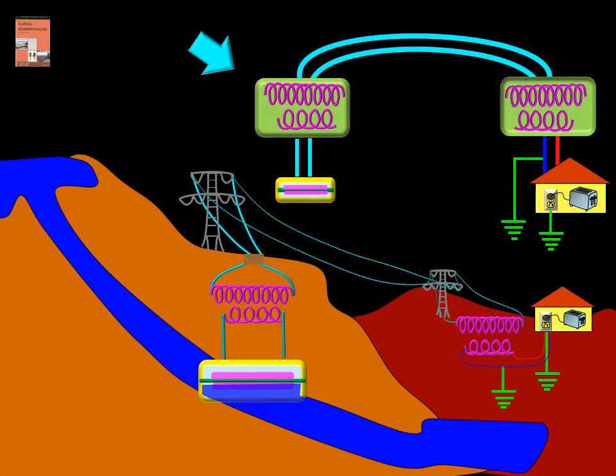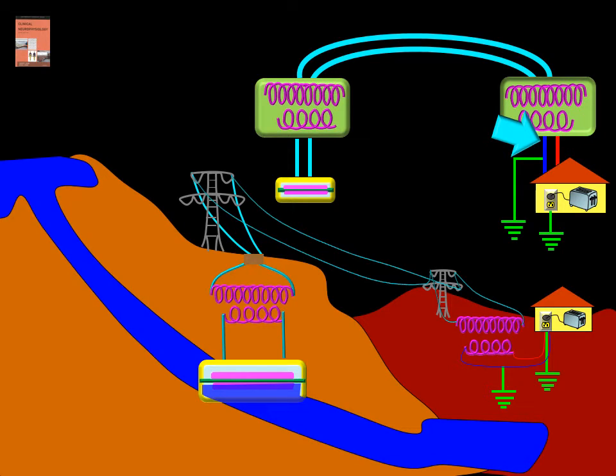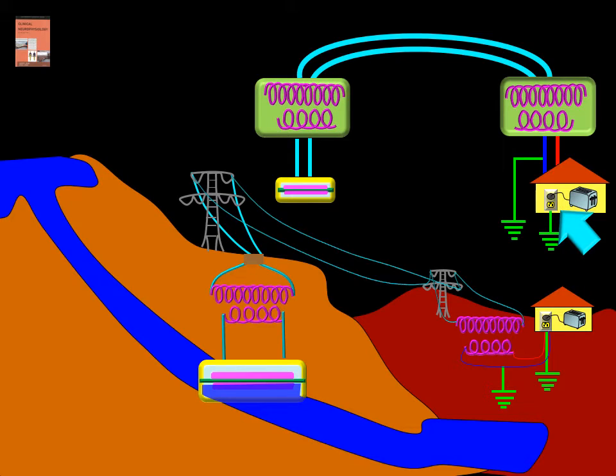The electricity produced by the power plant is boosted to deliver high voltage electricity in the range of 4,800 volts, which is then reduced by a second device to 120 volts, and once reduced to 120 volts it is delivered to the hospital to be available at the wall receptacle for powering hospital equipment. A schematic shows the entrance of electricity to the hospital: the hot wire bringing 120 volts, the neutral wire with close to zero voltage due to its connection with earth, and the hospital equipment connected to a receptacle independently connected to earth.